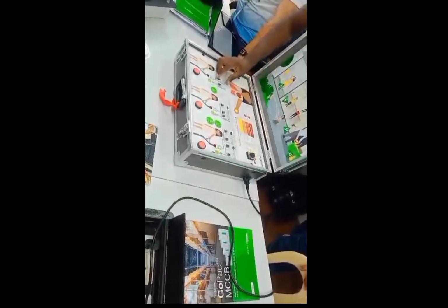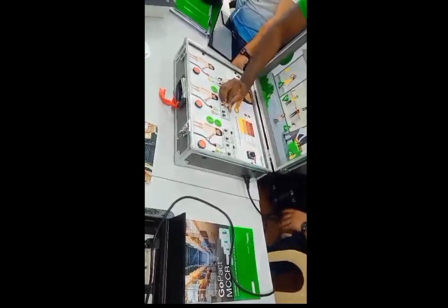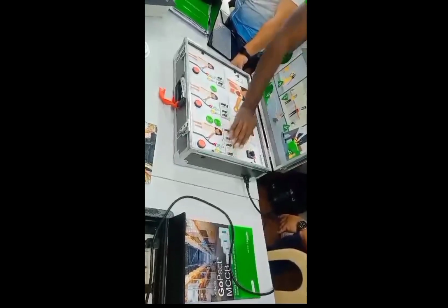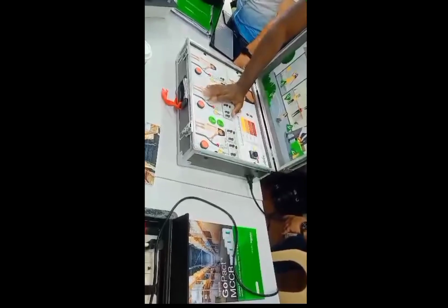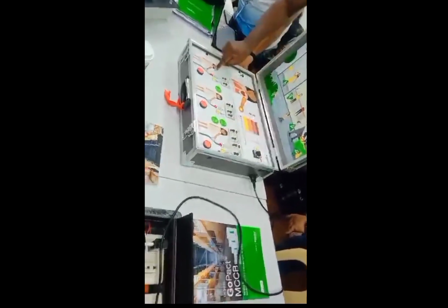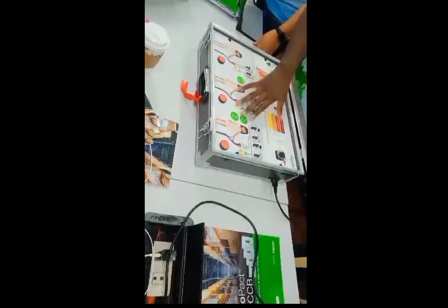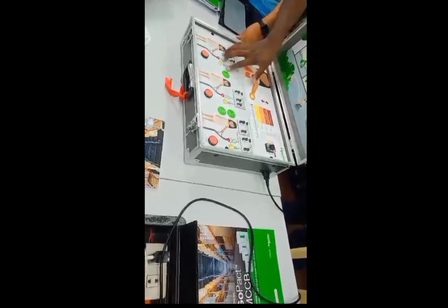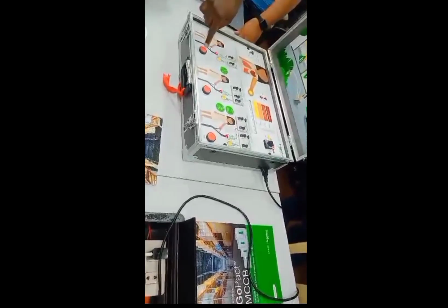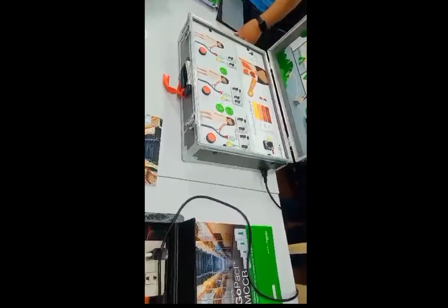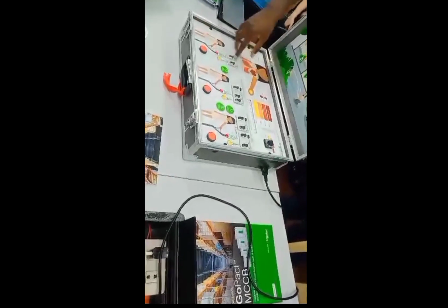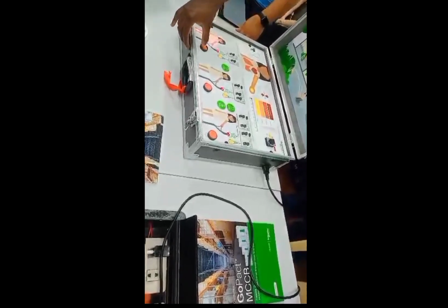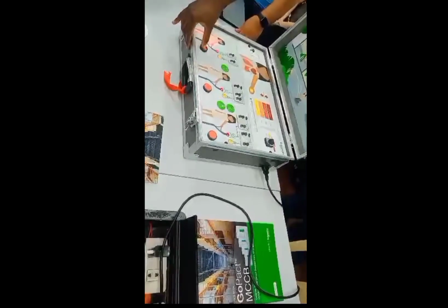Now here I want to show you, we have these 3 use cases to show you some of the continuity of service that you can get by segregating circuits. So the first one here, you have socket outlets, light circuit, and you have an MCB to protect them against short circuit and overload. So when I press this, it simulates earth leakage fault. So it will inject 30 milliamps into the system. So if I have just an MCB, the breakers will not trip. So it continues to shock the person.